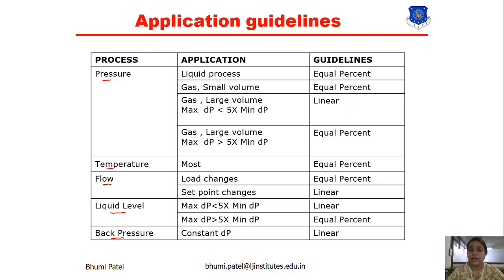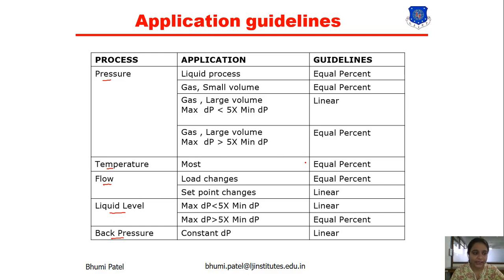This is the basic guideline for the pressure process. For the liquid process, we compulsorily use equal percentage. For the temperature process, in most applications, we use the equal percentage valve characteristic.